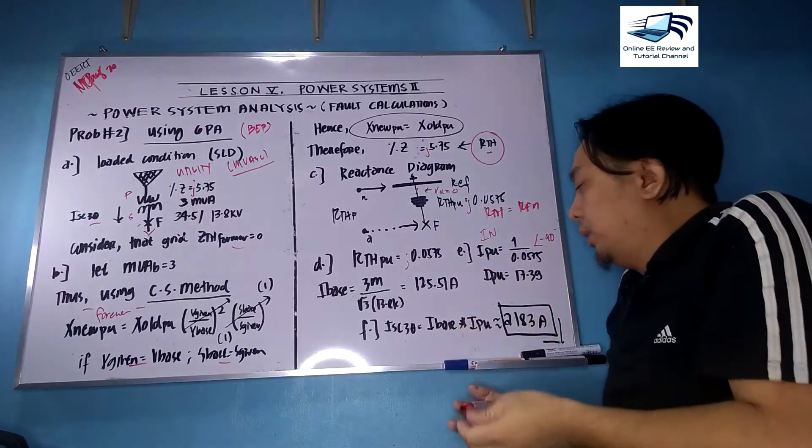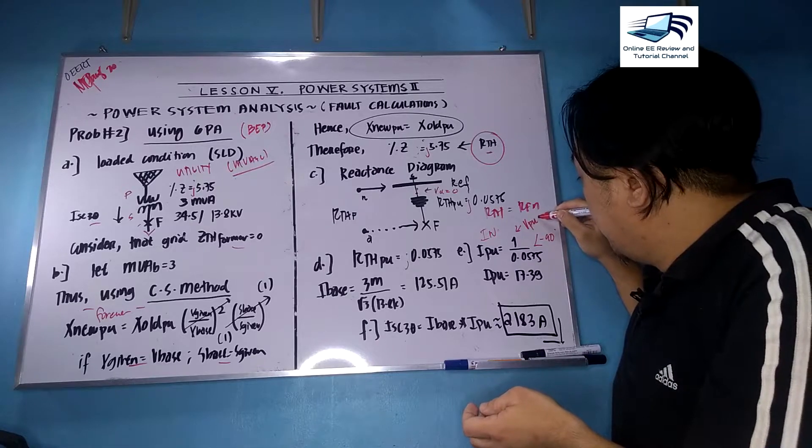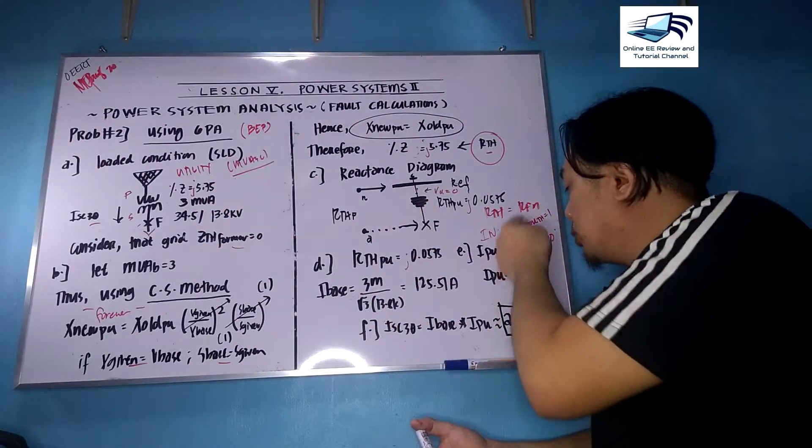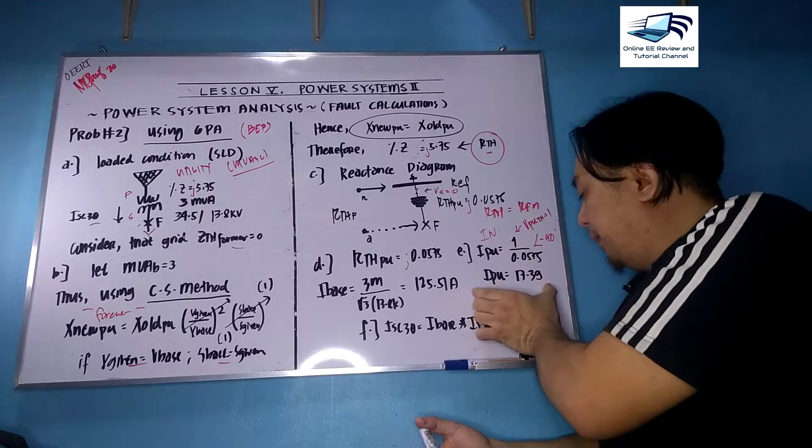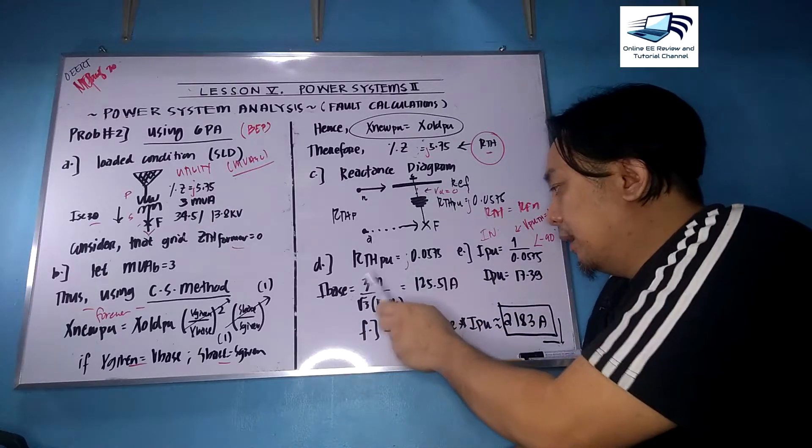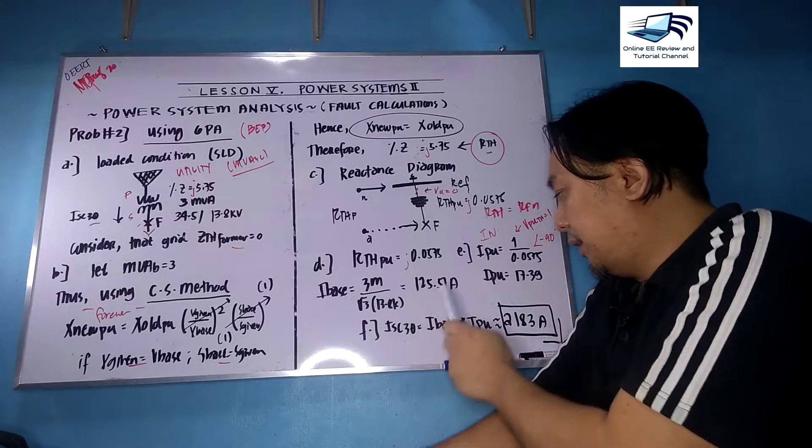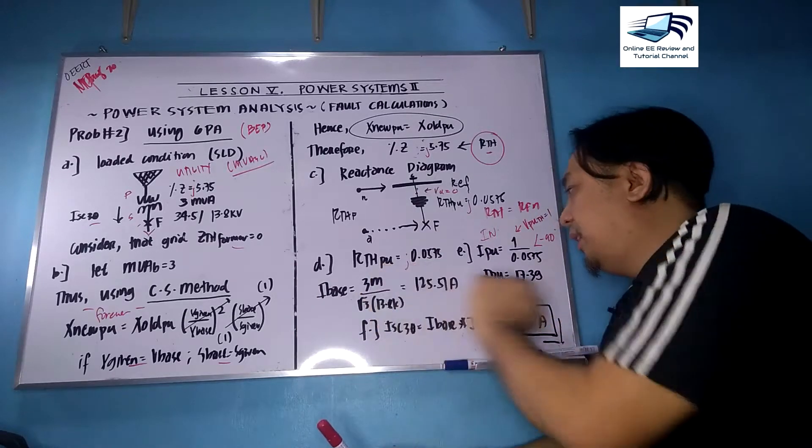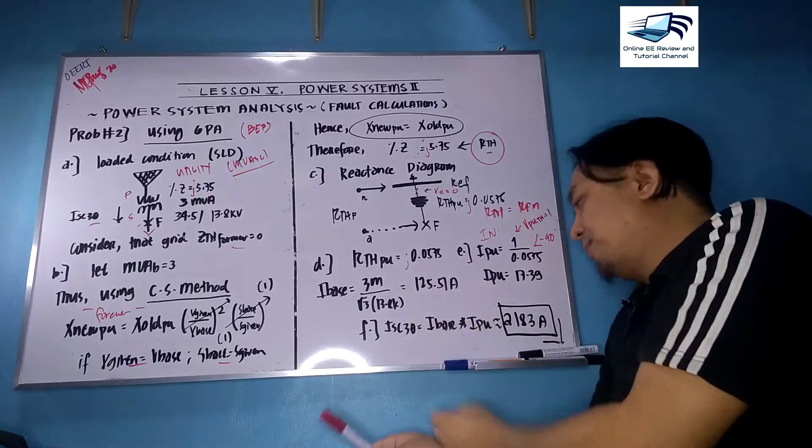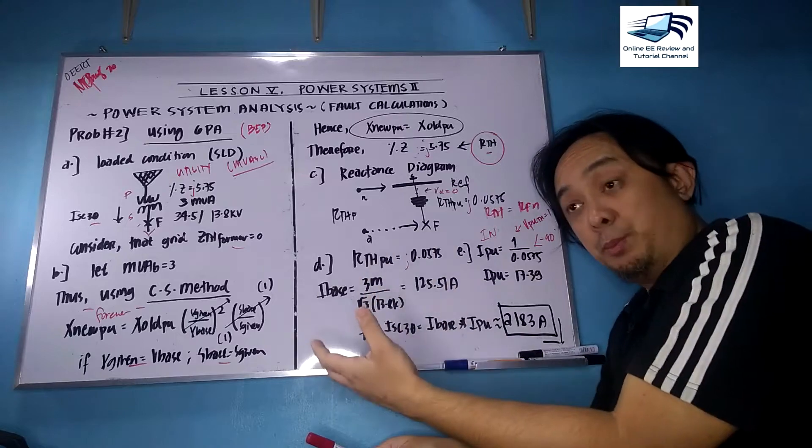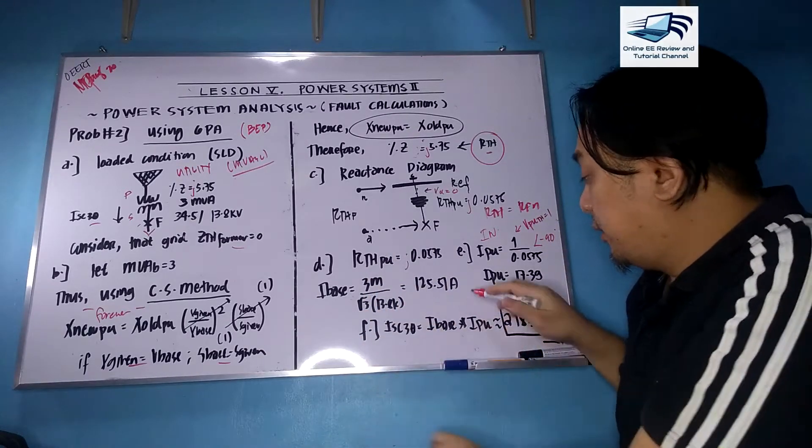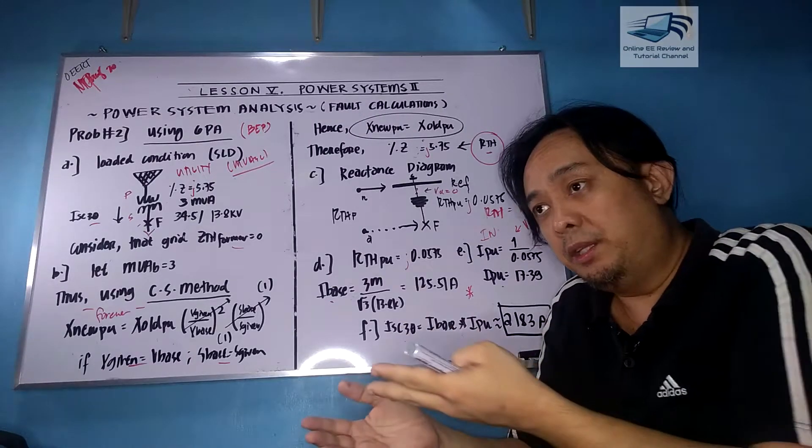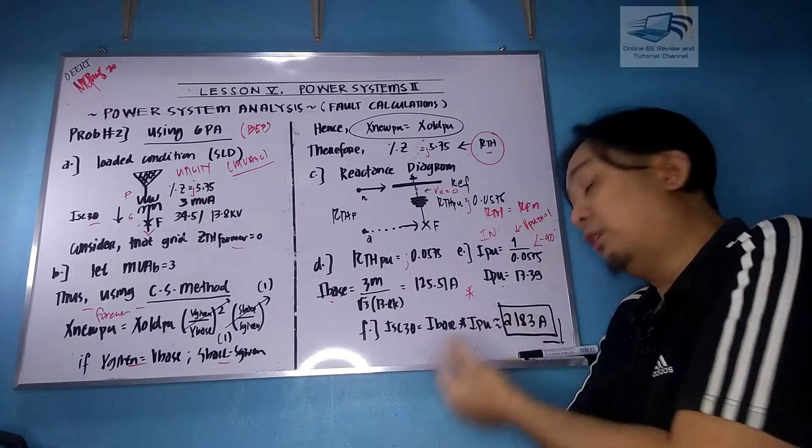Get the per unit current considering a linear system. Your per unit voltage at the fault is one because V given equals V base on the secondary side, 13.8. So 1 over 0.0575, the answer is 17.39 per unit. Then get I base: 3 million over square root 3 times 13.8k, the answer is 125.51. This is procedure number five: get I_PU and I base. Last but not least, the sixth procedure: get ISC three-phase by multiplying I base by I_PU. The answer in this board problem is approximately 2182.6, but we can round it off to 2183 amperes.